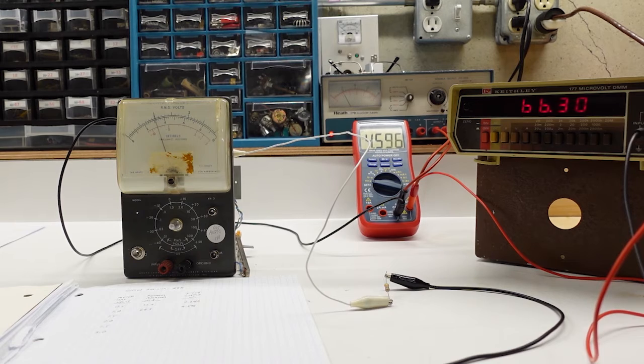The next test is to confirm the linearity of the meter. What I want to do is apply progressively increasing current up to the 200 microamp full scale and compare the meter reading to a reference ammeter of sufficient accuracy. So, for this test, I'm using my trusty Keithley-177, which I previously checked against a calibrated lab instrument and know its accuracy.